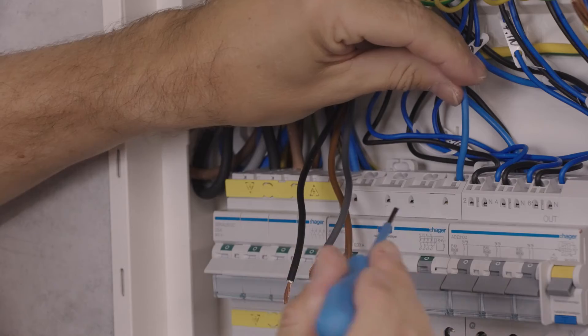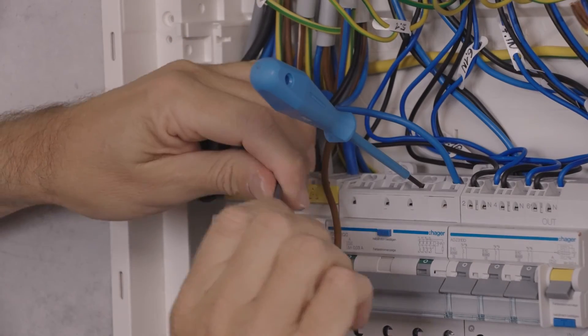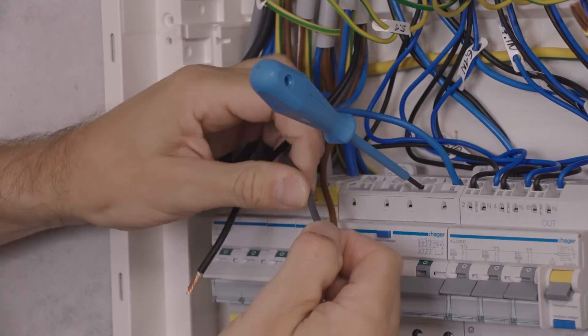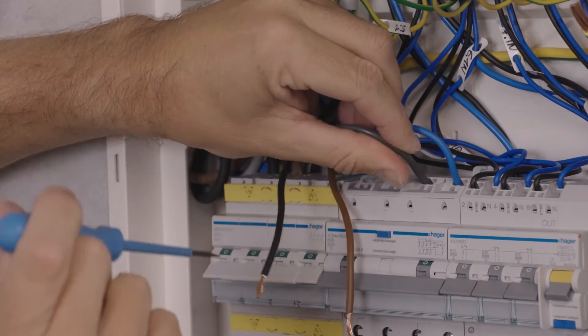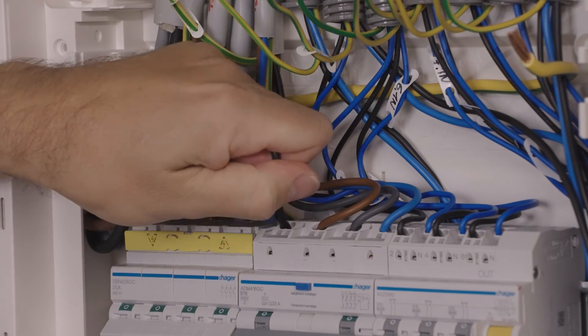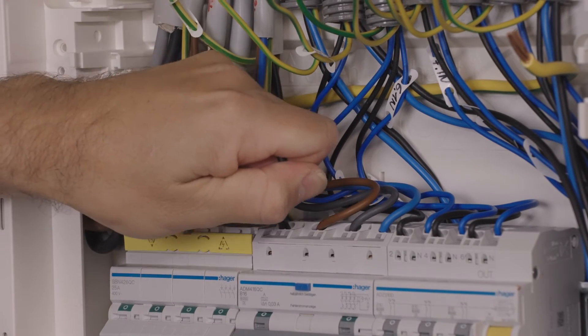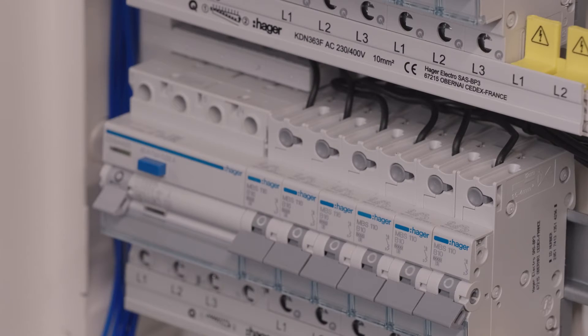When using a flexible wire, you must use a flat 2.5 mm screwdriver to insert it into the Quick Connect terminal clamp. Once inserted, there's no risk of loosening the connection — the cable cannot be pulled out of the QC clamp without intent.